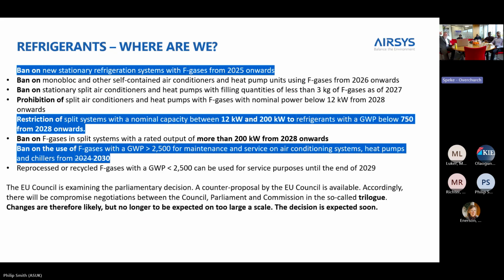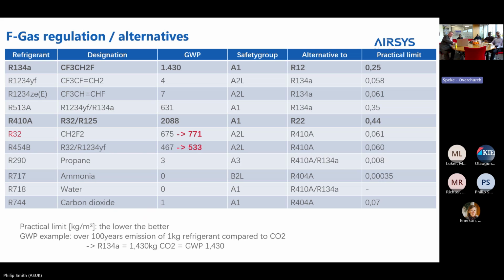They are going back. So just like the delay in getting rid of gas boilers in your houses, getting rid of refrigerants seems to be going back in timescale because the products to replace them just aren't there. We use 410A, which has got a GWP of 2088. Generally, if you want to lower the GWP, you either have a less efficient refrigerant that gives you less duty, or you have one that's flammable. And the industry is reluctant to use flammable refrigerants, but they still want the efficiency.